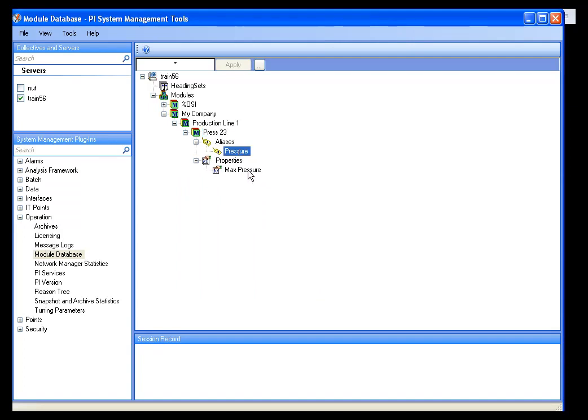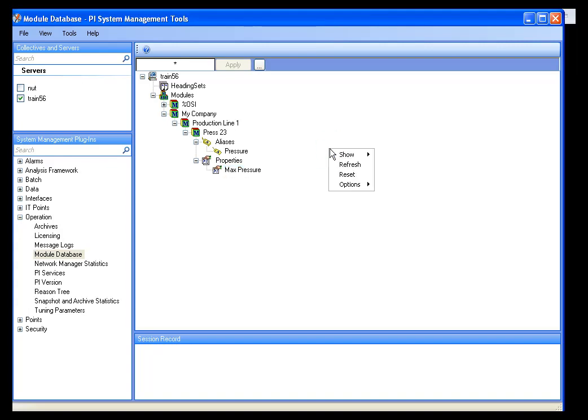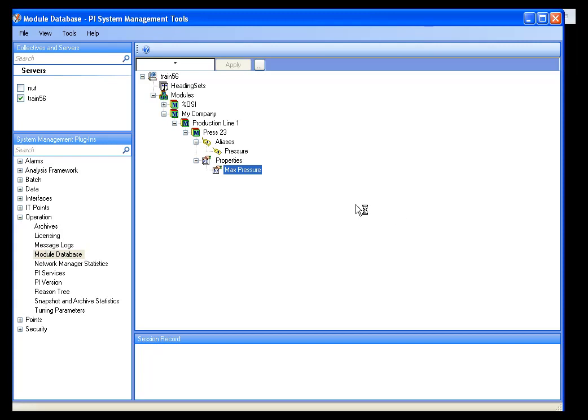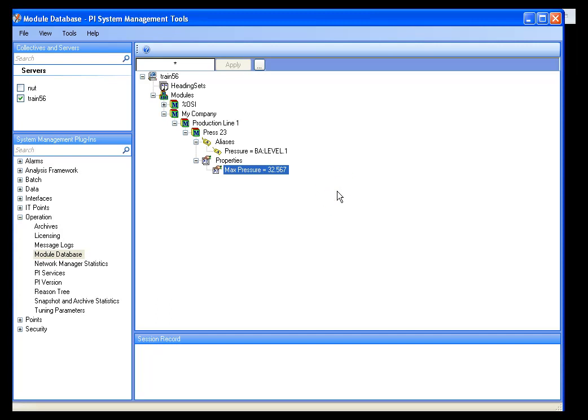We can see that we have Pressure and Max Pressure. If I want to actually see what these values are in this view, I right-click in the open area and select Show Aliases and Property Values. That will show me what my pressure tag is and my max pressure. I can now use these elements in a display or in a report — I can look at the current value for pressure and compare it to my max pressure in a trend, report, or something else.